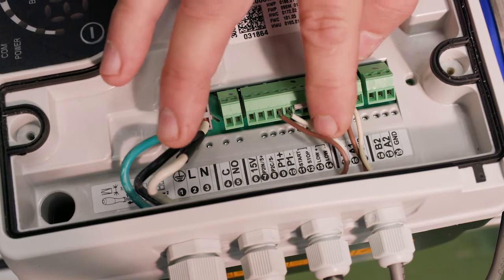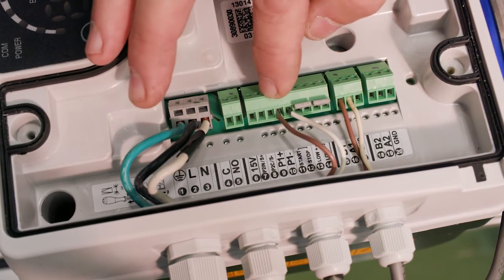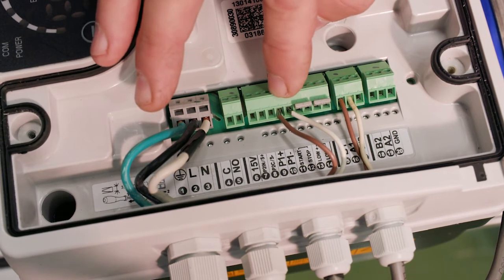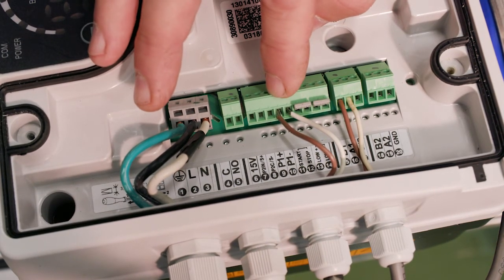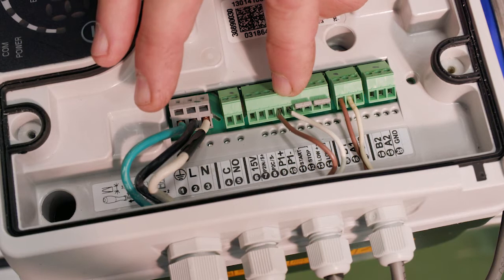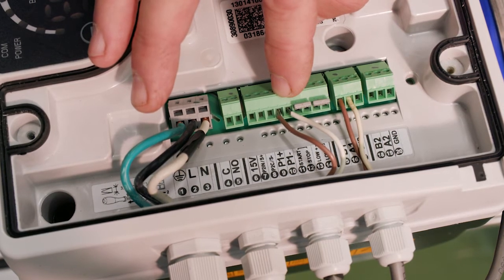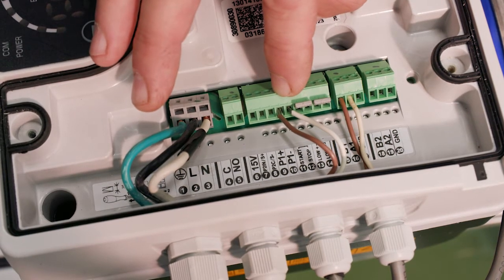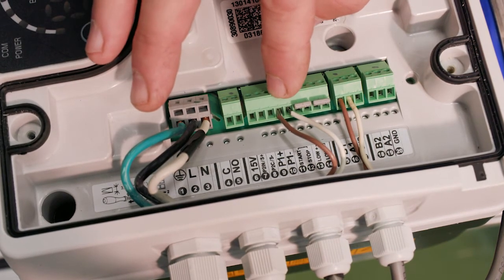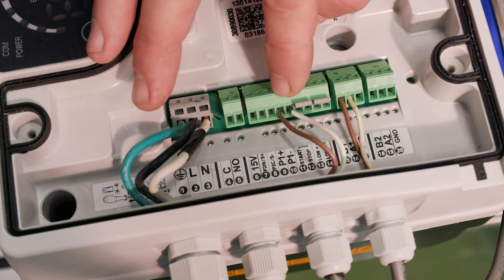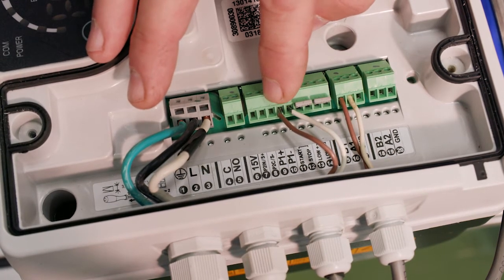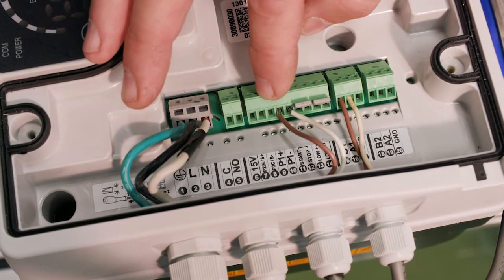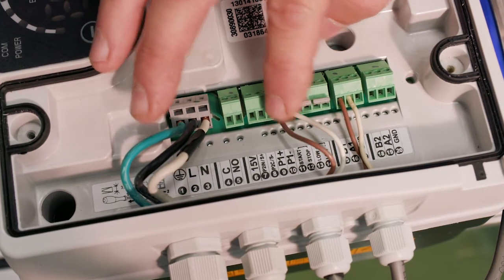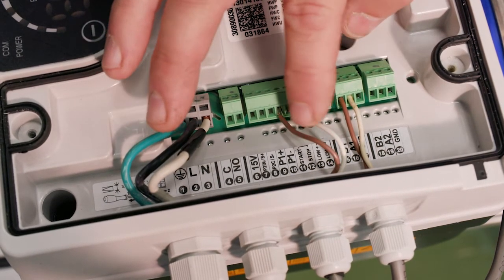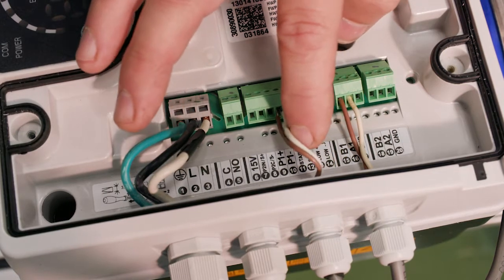But now we see where we have to do some wiring. This is terminals 9 and 10, P1 plus and P1 minus, and this is simply our sensor or transducer. Each unit has to have its own transducer. Typically our transducer cable is white and brown. We want to put the brown on the positive, terminal 9, and then the white on the negative, terminal 10.